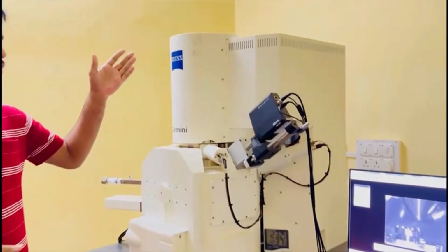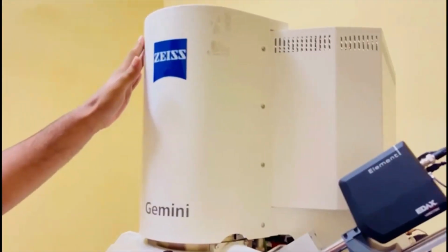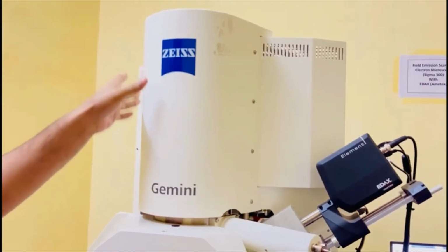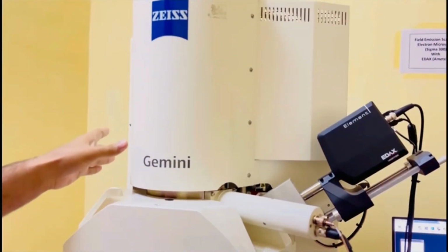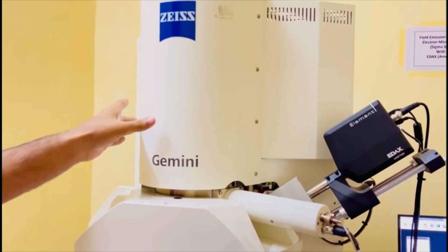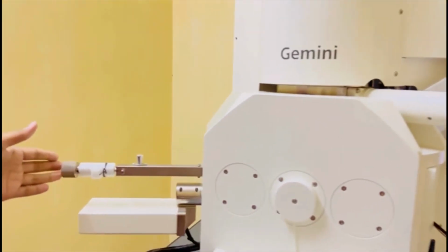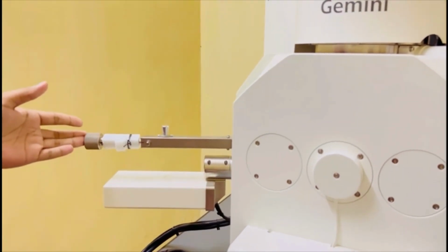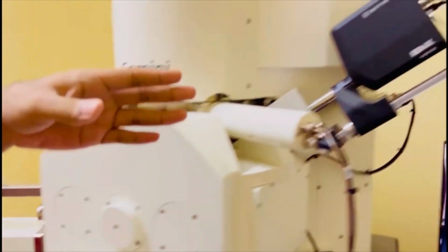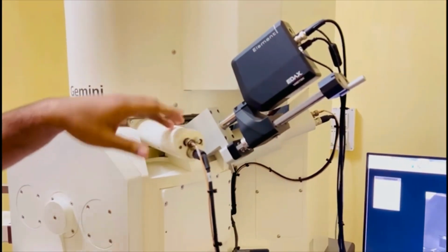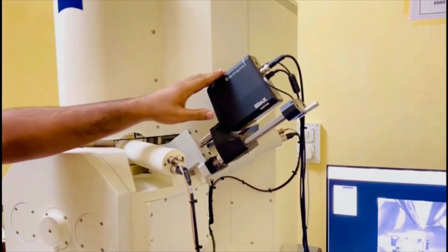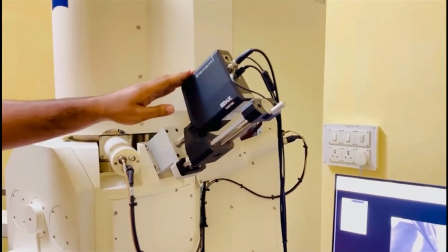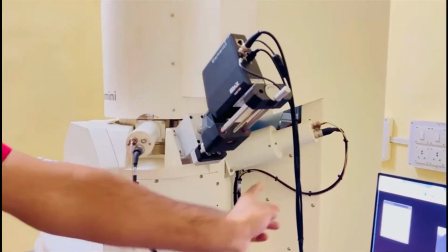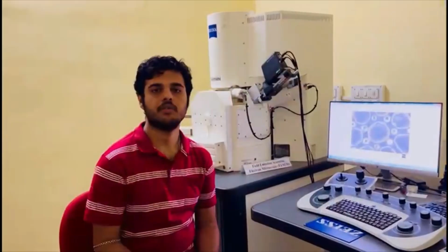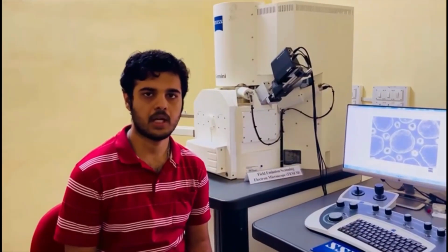The various parts of this machine include the FEG gun, and this is the column where the various scan coils, condenser lens and aperture are present. This is the detector for backscattered electrons. This is the detector for in-lens, and this is the detector for EDX, which is used for elemental analysis and mapping.